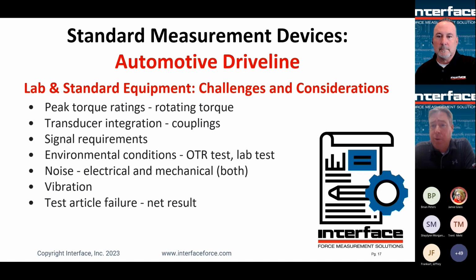Vibration: making sure that the rotating assembly is balanced well. If you have a shaft that's not aligned correctly or has a balance issue, you can end up shaking the transducer more than it's designed to handle, which can lead to failure. So make sure your rotating assembly is balanced sufficiently for the application and RPM range.